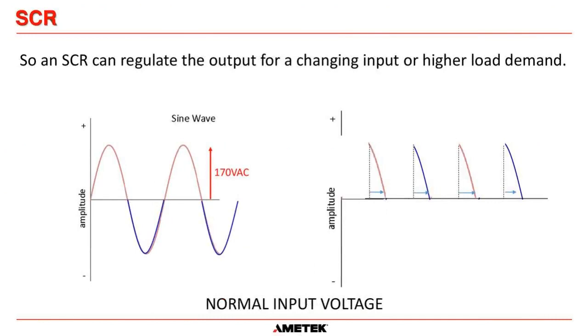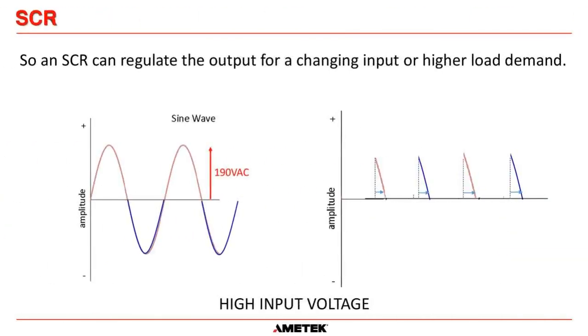And then if our voltage went back to 120 volts, with peaks up to 170 volts, we're switching the SCRs on this side, regulating the output. The level of the average of this output is the same as the previous one. And if the input voltage goes high and the peaks go to 190 volts, we switch the SCRs on really late in the cycle, and our average still remains the same. So basically, where we switch the SCRs on determines the average output of the rectifier circuit.